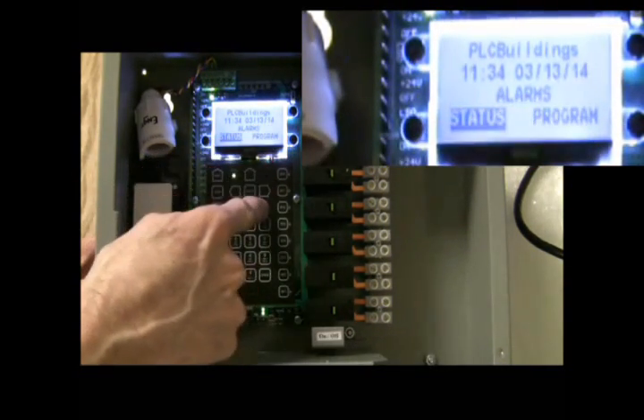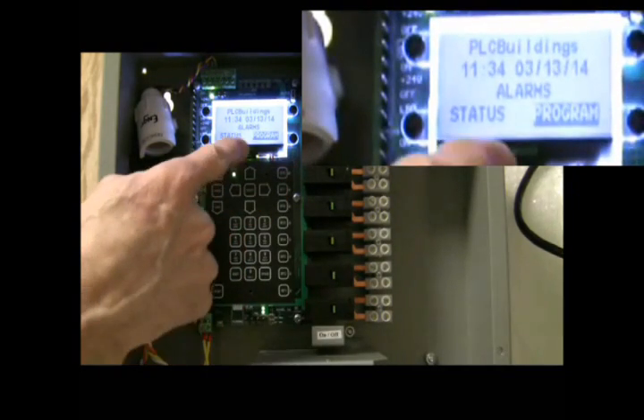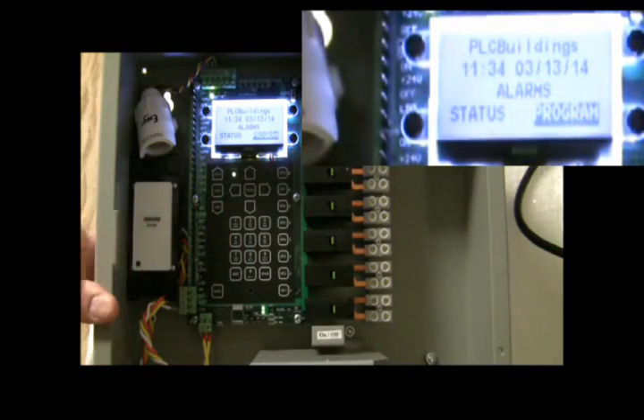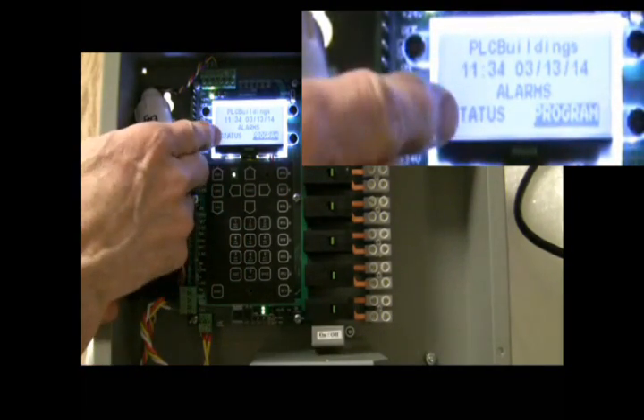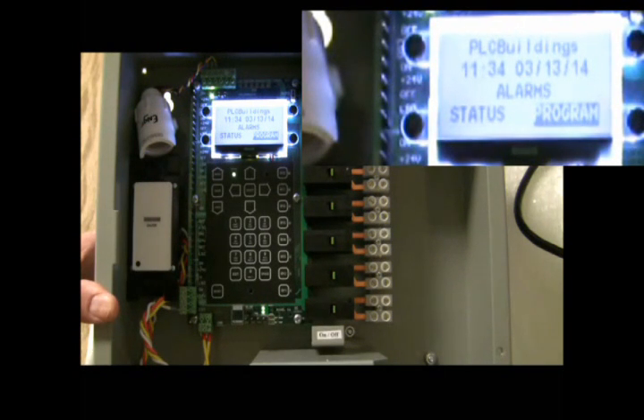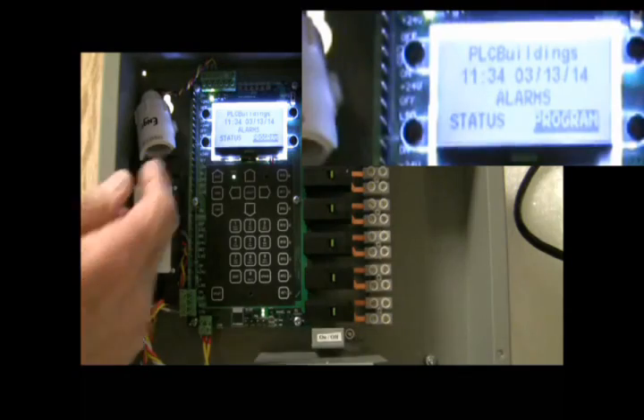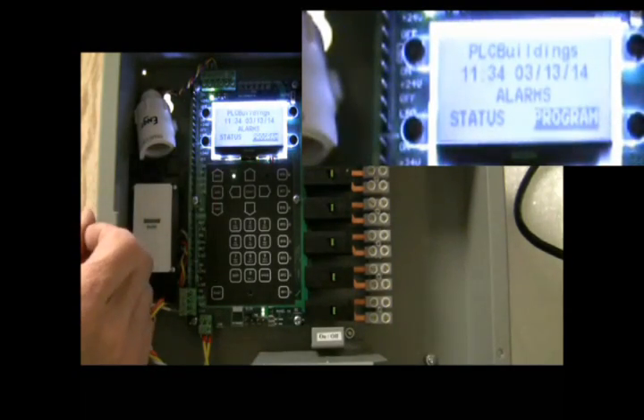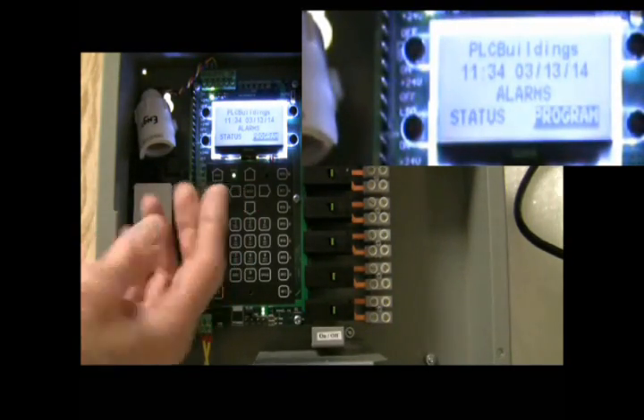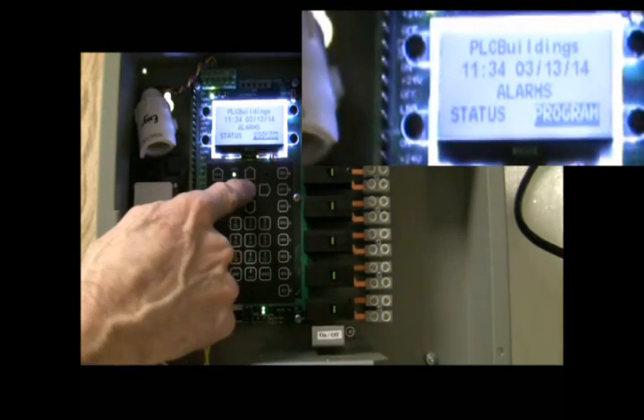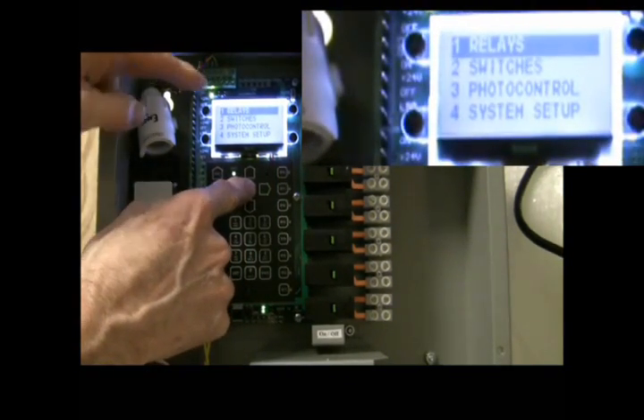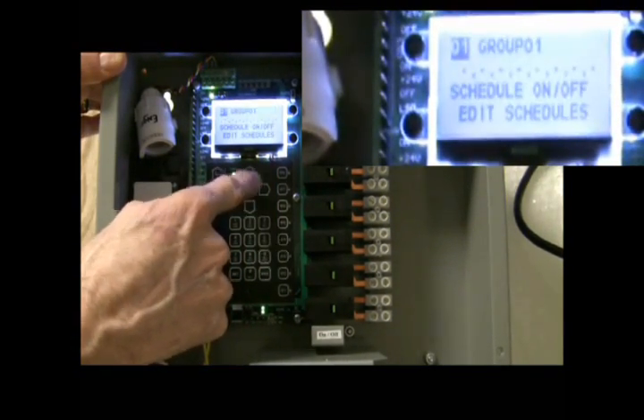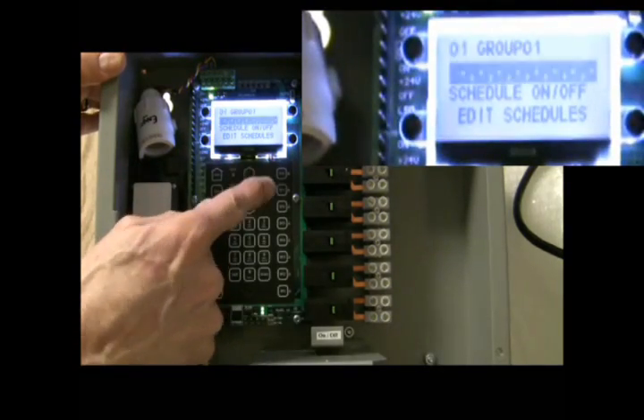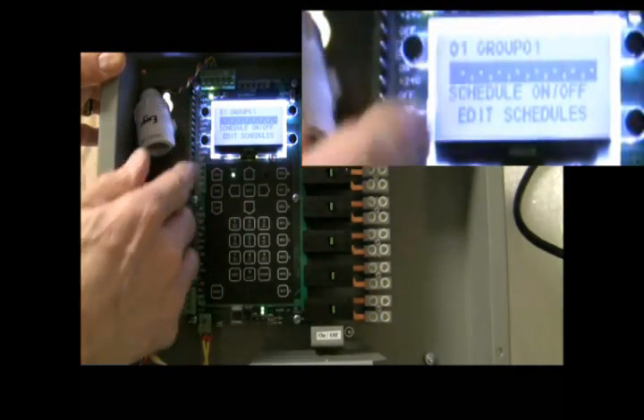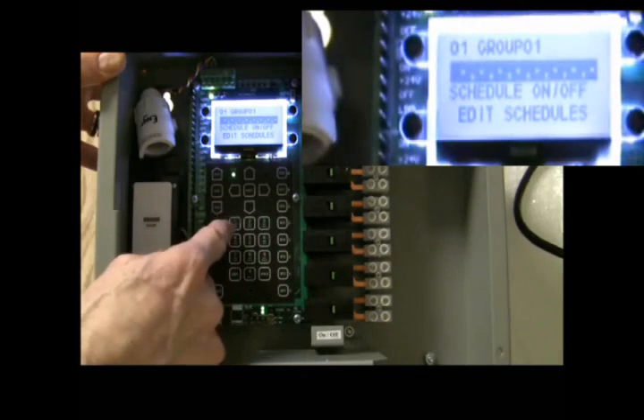You have to be in program mode to actually create a program. The status is for looking at the status of the relays and whatnot, and it's a read-only aspect. So we go to program. What we're going to do is set up a group of four relays, group one. So we're going to program, relays, groups. You can see the second line is for selecting the relays within group one. We'll set up the first four relays.